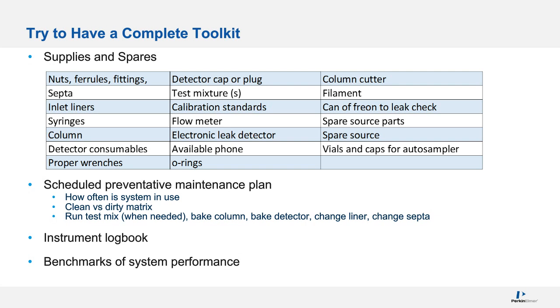There's one thing that I would like to point out on this list. Well, 2 things. Detector cap or plug. The detector cap or plug is used to isolate the detector. So if there is a problem and we're troubleshooting, we like to isolate parts of the instrument to make it quicker in finding what actually the problem is. The ECD plug is different than the mass spec plug. It's just a plugging ferrule. For the ECD, we use a 1/8-inch Swagelok. For the mass spec, it's a 1/16-inch plug with a plugging ferrule, a ferrule that doesn't have a hole in it. So those are really important.